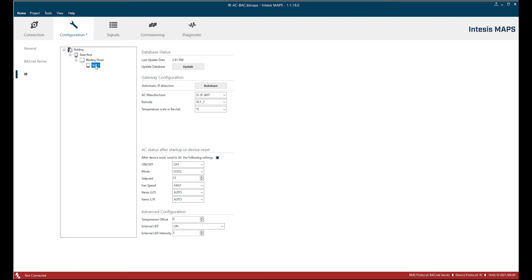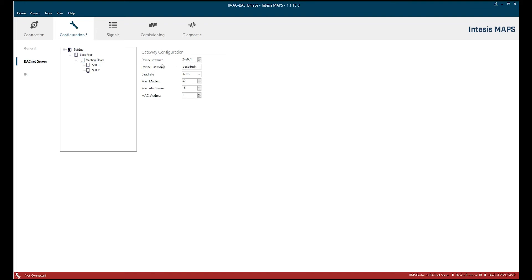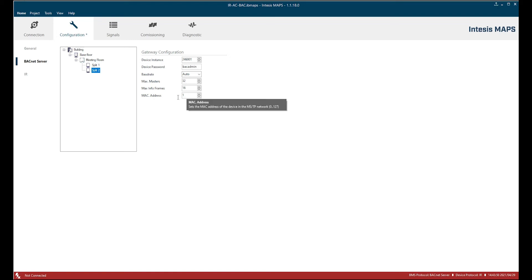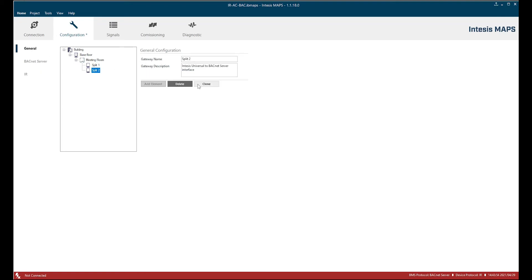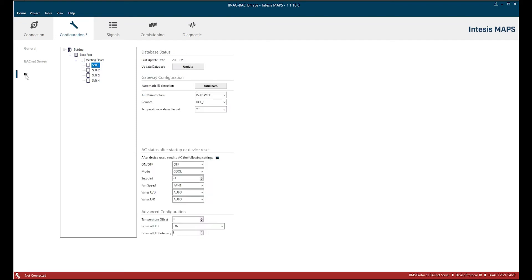So now I configured the first unit the split unit split one and this is very convenient. I can clone it so let's clone this device. I have a second one which has the same name. I just need to rename it and we will see on the BACnet server subsection that the device instance and the MAC address are sequentially numbered. So on the first we had the MAC address 0 and the device instance finishing on 0 and on the split 2 we have the device instance finishing on 1 and the MAC address finishing on 1. We can do this again and again as many times as we need for split 3 for split 4 and this is very convenient if you have several times the same split unit or at least having the BACnet side pre-configured.